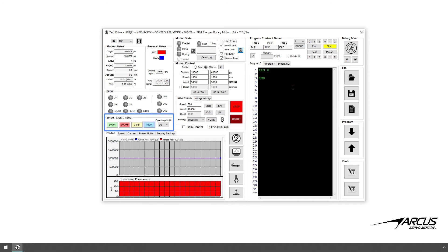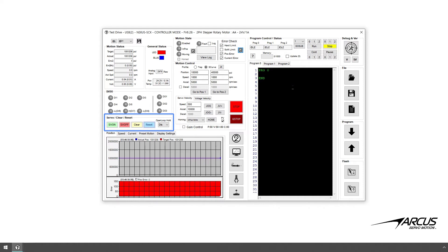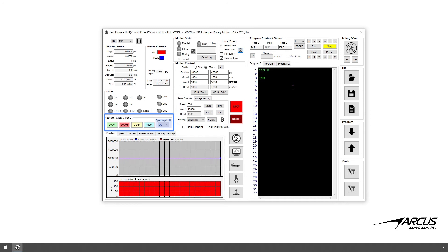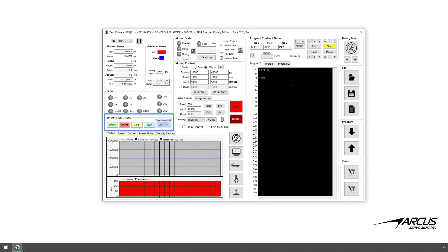The reset button will reset the servo on the initial phase angle value. This reset applies to stepper servo motor control and brushless servo motor control without hall sensors, where the initial phase angle is determined with a slight movement of the motor at servo on. Once the initial phase angle is determined at servo on, this value remains in memory until a fault or reset occurs. The open loop hold selection list applies only to the stepper servo control. When an open loop hold is selected other than disable, the stepper motor goes into open loop mode in idle or when not in motion; when the motor is in motion it goes to servo control mode, and when not moving the stepper motor goes into open loop constant current mode.